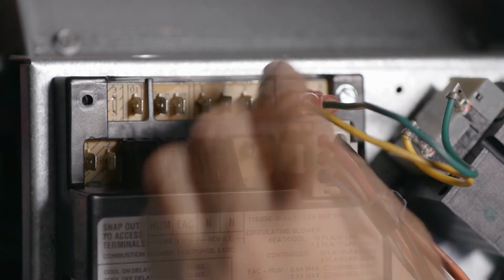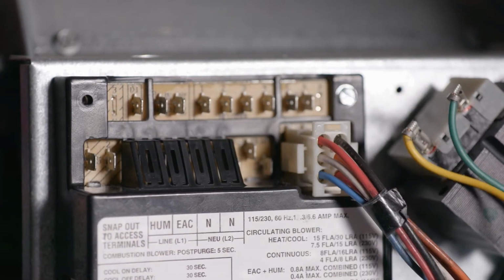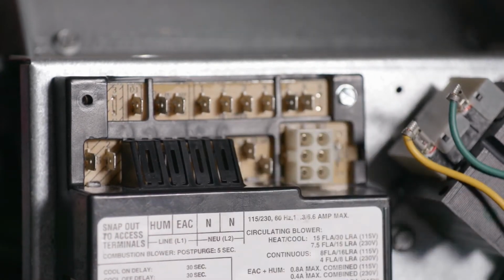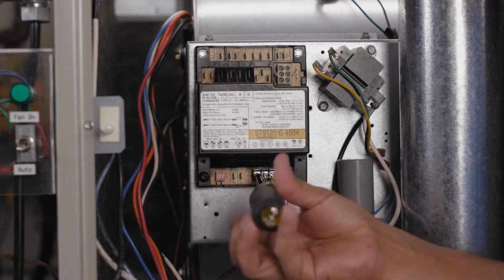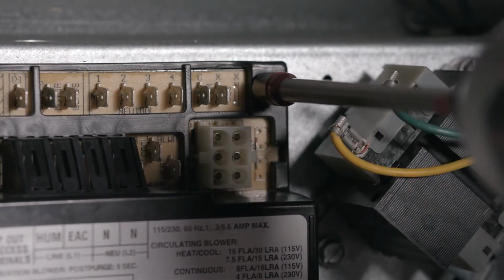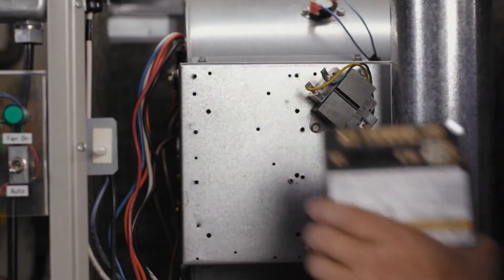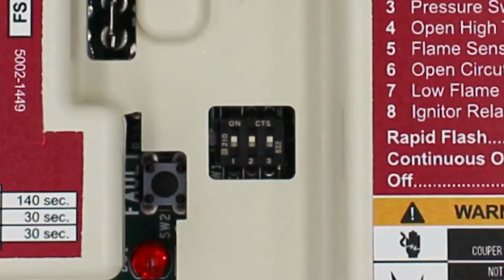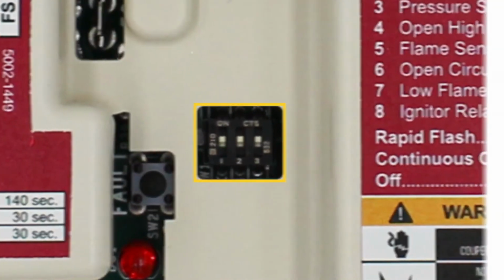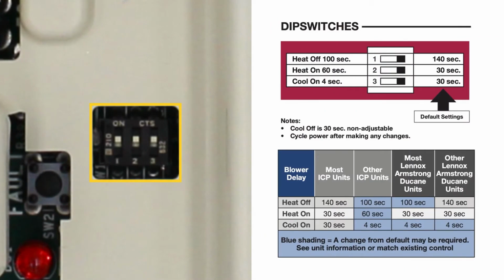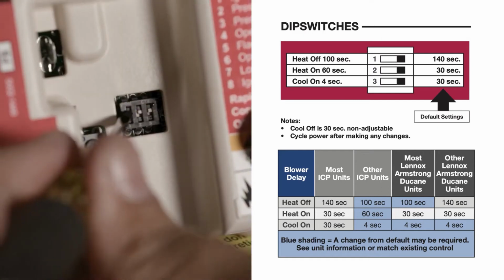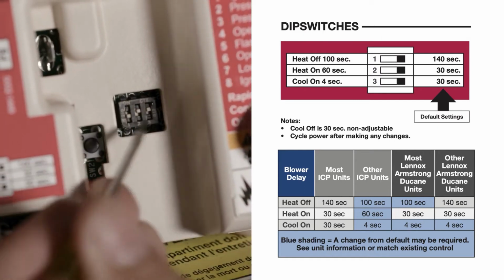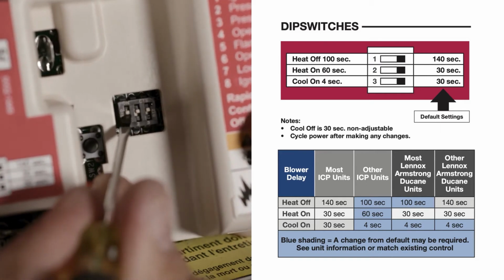Remove the 120-volt hot and neutral transformer wires. Remove the 24-volt transformer wires. Disconnect the 6-pin Molex plug. Disconnect the thermostat wiring. Finally, remove the fan timer. Dip switches control the blower on and off delay times. Dip switch settings should match the existing control. To change the dip switch settings, use the dip switch configuration chart located on the control cover and with a small screwdriver, move the switch to the correct position. For this application, no changes are needed.